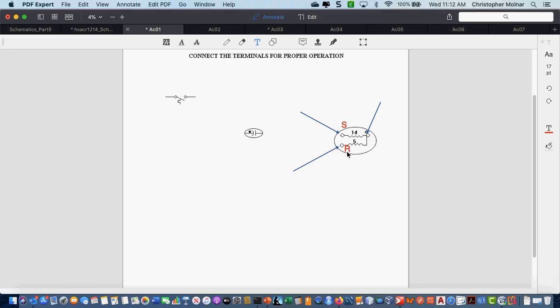So even though in this diagram run and start are not labeled, you'll always know that your run terminal is the lowest resistance between run and common. Your start terminal is the highest resistance between start and common. Okay, any questions on that? Nope.